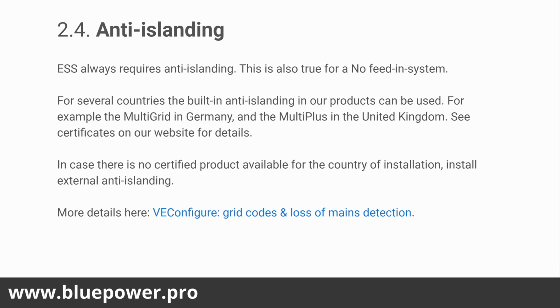So that's where it's a requirement to have anti-islanding, like in the city of Cape Town municipality. So if you're installing a Multiplus-II inverter, you're going to have the anti-islanding built in, and that's already compliant with the city of Cape Town for the regulatory requirements for South Africa. And the Quattro-II inverters are also in the process of being approved. So they are compliant, but not approved yet. But the older Multiplus or Quattro inverters aren't compliant at all.